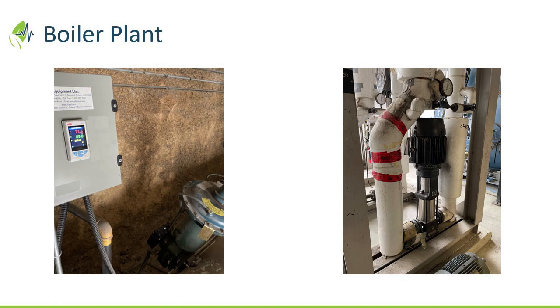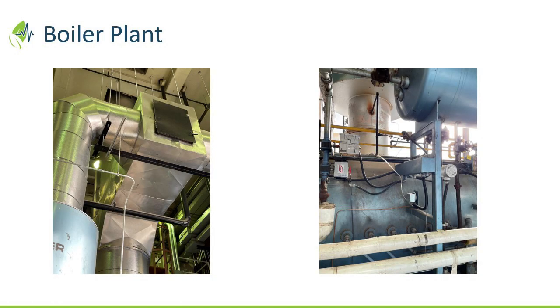So the new boilers have the controls which tell you if the economizer fails. With the old boilers, how could you detect it? Can the color of the smoke tell you if your boiler economizer is not working, or has failed? For example, if your economizer is not fully functional, the new boilers have the controls which tell you if it fails. But if I'm talking about an old boiler, like for example, one I visited, is there any indication, any kind of color of the smoke, anything you can tell other than to go and troubleshoot and find it out? No, the only way is temperature indication.